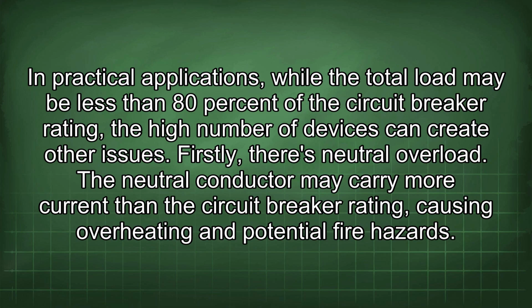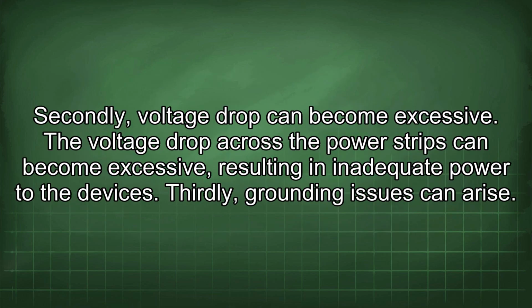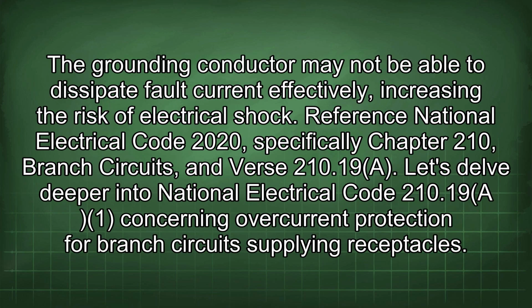Firstly, there's neutral overload. The neutral conductor may carry more current than the circuit breaker rating, causing overheating and potential fire hazards. Secondly, voltage drop can become excessive. The voltage drop across the power strips can become excessive, resulting in inadequate power to the devices. Thirdly, grounding issues can arise. The grounding conductor may not be able to dissipate fault current effectively, increasing the risk of electrical shock. Reference National Electrical Code 2020, specifically Chapter 210, Branch Circuits, and section 210.19(A).